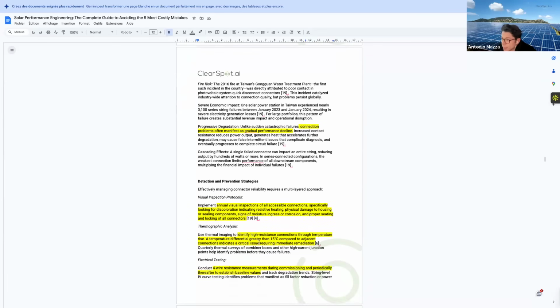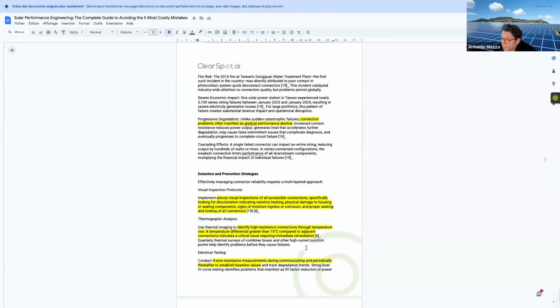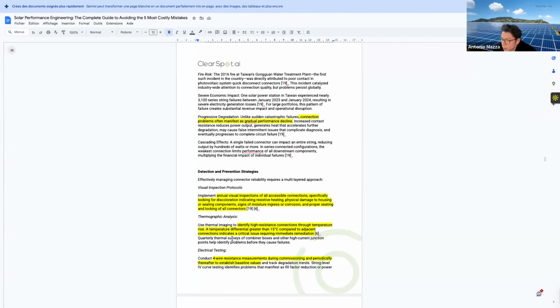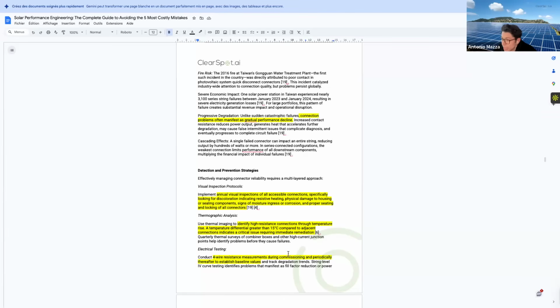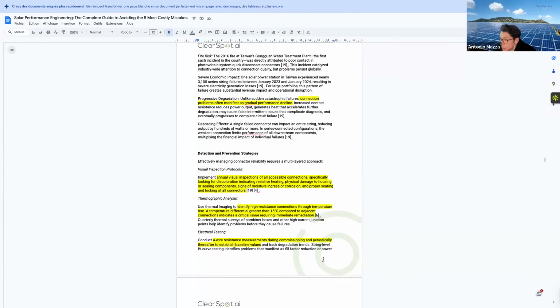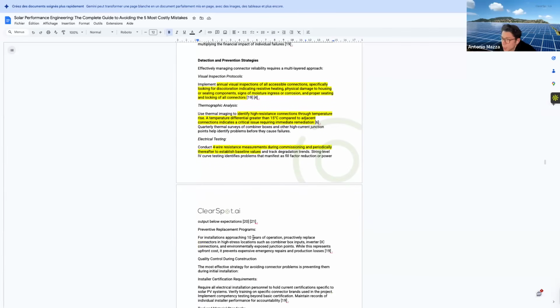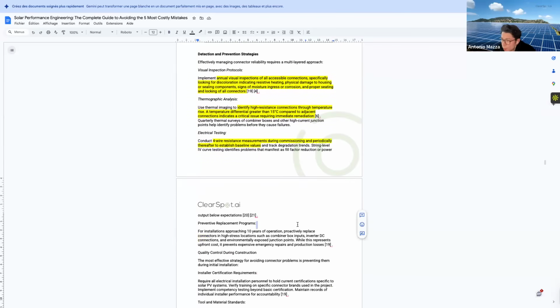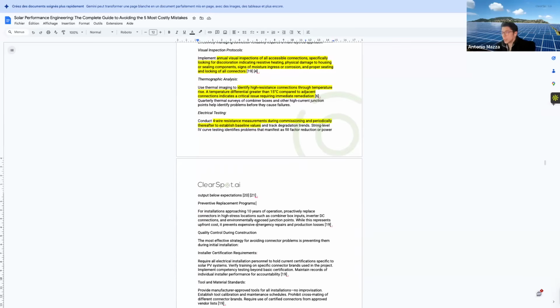Thermographic analysis: you want to do this in order to identify a temperature rise, one of the main indicators. A rise greater than 15°C compared to adjacent connectors indicates a critical issue requiring immediate remediation. Electrical testing: 4-wire resistance measurements during commissioning and periodically thereafter to establish baseline values. Then there are preventive replacement programs. Installations approaching 10 years of operation should practically replace connectors in high-stress locations like combiner box inputs, inverter DC connections, and environmentally exposed junction points. While this represents an upfront cost, it prevents expensive emergency repairs and production losses.